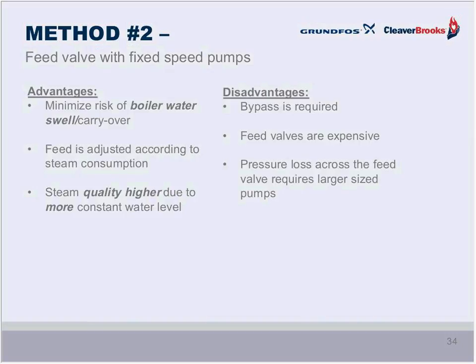Advantages: that carryover or swell that we talked about earlier can be minimized. We do have the feed water adjusted according to the steam consumption. And the quality of steam is higher because we have a more constant water level. It's not constantly jockeying up and down to such a great extent. But disadvantages, there's that bypass, that wastes flow. Feed valves are expensive. They have to be maintained, and you also lose a lot of pressure across them. So those are some of the challenges.